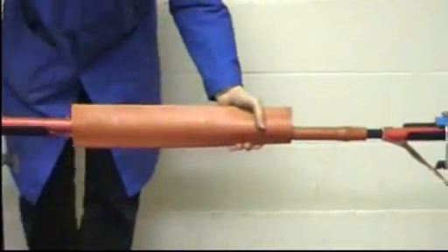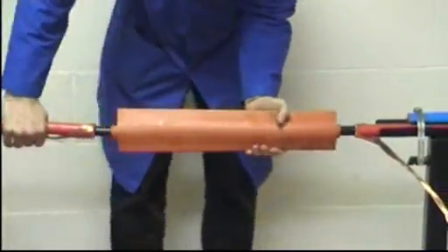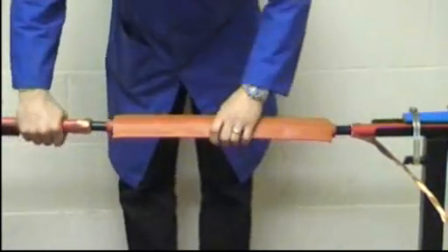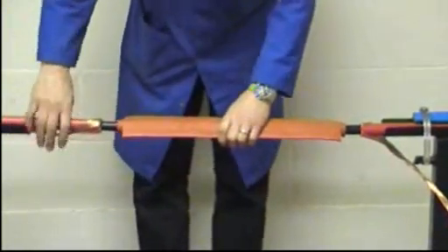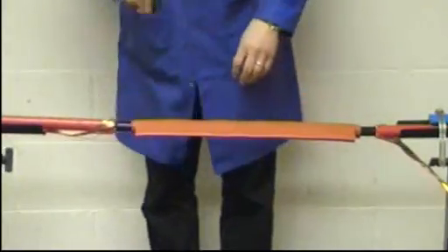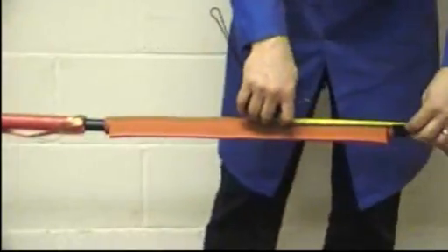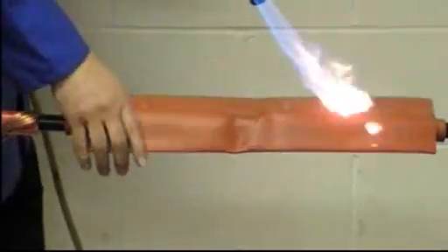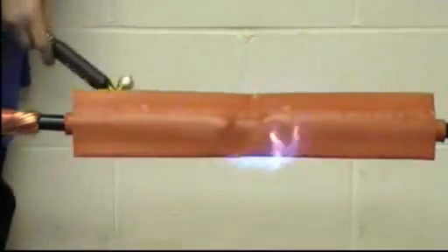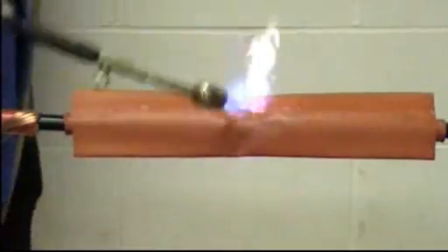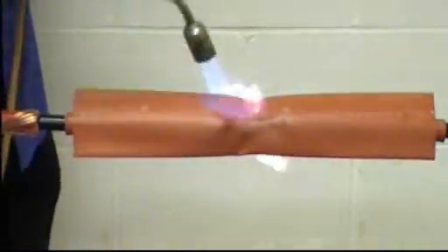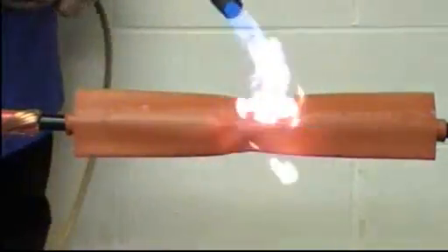At 33 kV, two additional red tubes are fitted over the stress tube to give us the insulation required. At 17.5 and 24 kV, only one additional red insulation tube is fitted. Whereas at 33, there are two.